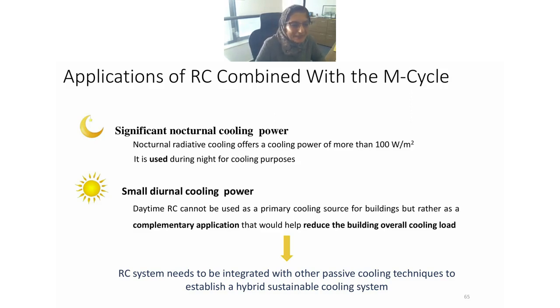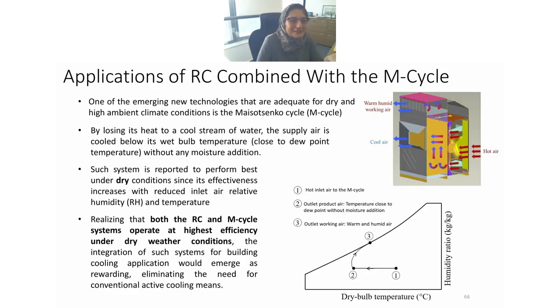What we chose was the M cycle. Some of you may wonder what this M cycle is—it's basically an indirect evaporative cooler, a device or equipment that is commercially available; you can buy this from the US, from China, from Europe. On a psychrometric chart, it sensibly cools the air to almost its dew point, instead of cooling the air to the wet bulb temperature, so I end up with a much lower temperature than the wet bulb temperature normally achieved with direct evaporative cooling. In the indirect M cycle, you have two streams going in opposite directions in two different channels: one channel has a wet water film and the other channel is dry.